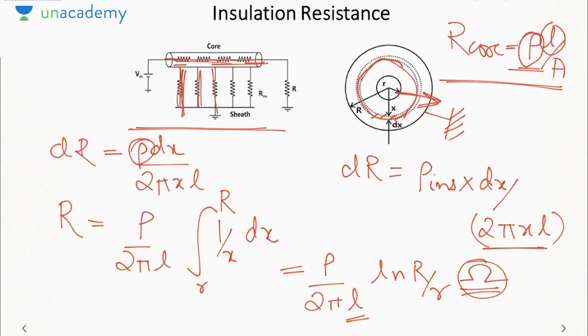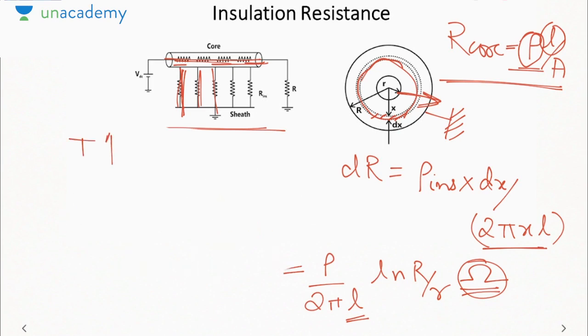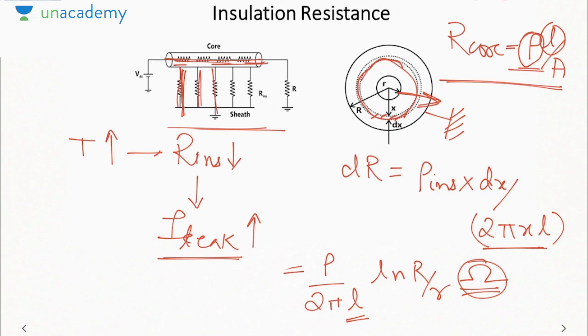Now insulators have a negative temperature coefficient. Why? Because as the temperature increases, the thermal energy in the atoms will increase, which can lead to ionization of electrons. So charge carriers will increase as we increase the temperature. And if we increase the number of charge carriers, the conductivity will increase and the resistivity will go down. So the resistance reduces as we increase the temperature in an insulator. Okay, so they have a negative temperature coefficient. So what I am saying is, as temperature increases, insulation resistance decreases, due to which leakage current will increase. There will be more leakage from the conductor to the ground. So higher temperature is undesirable in a cable, as it leads to more leakage.